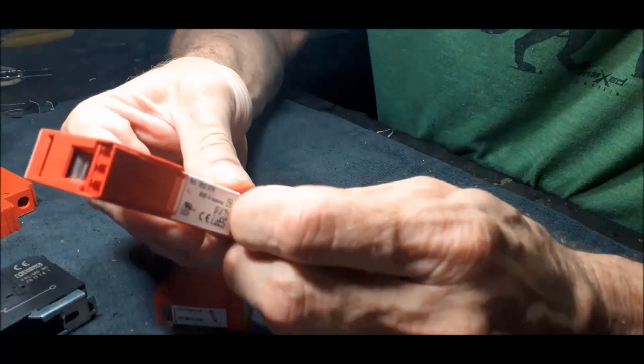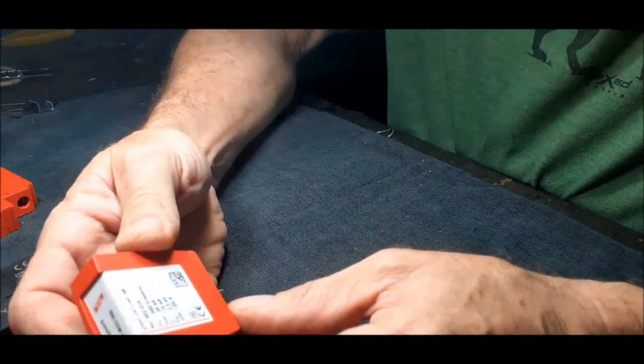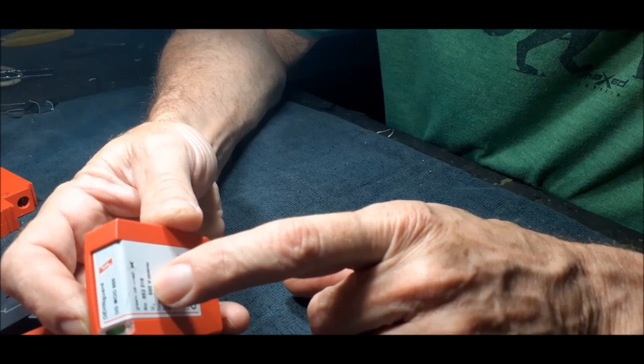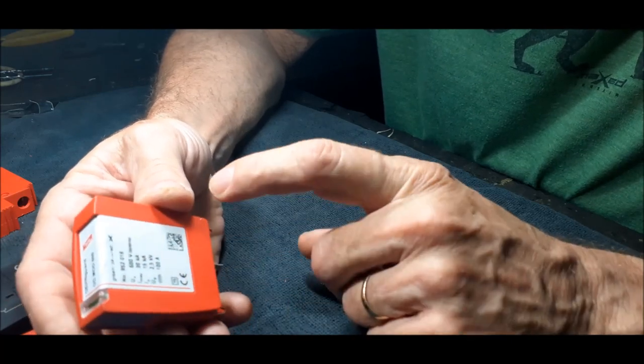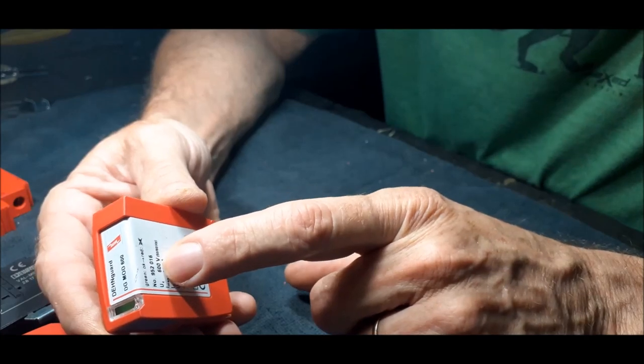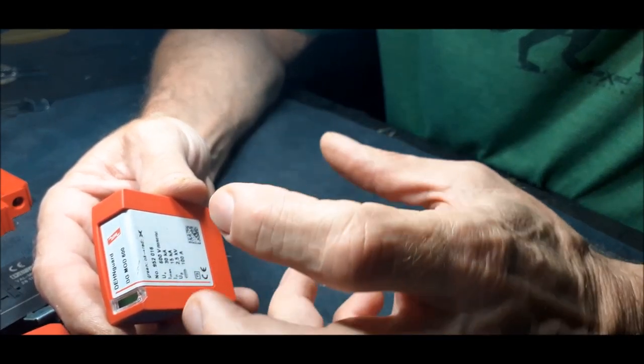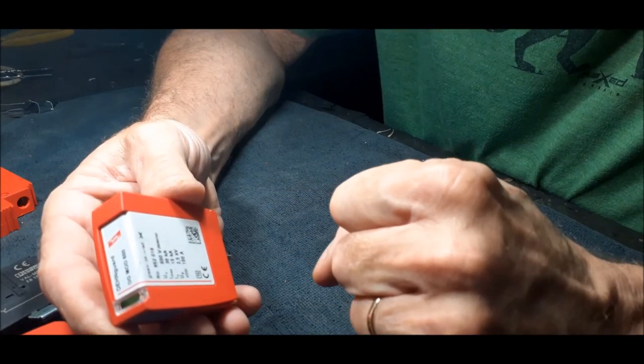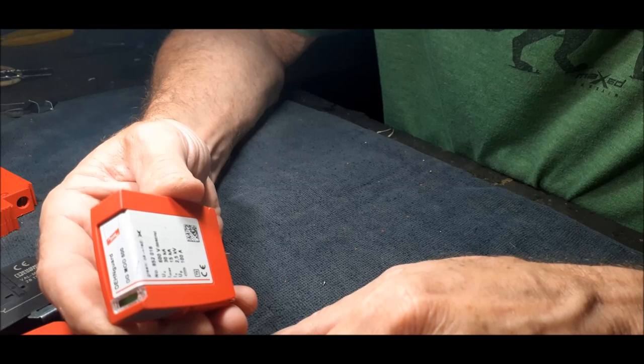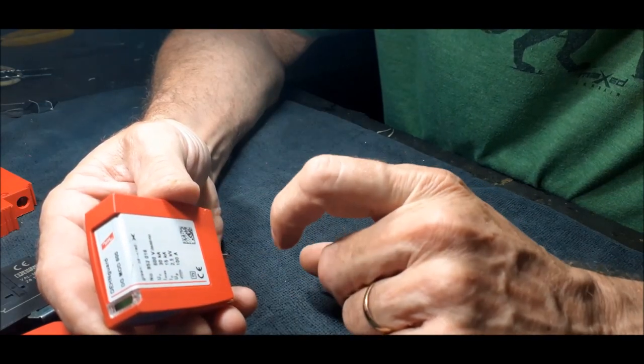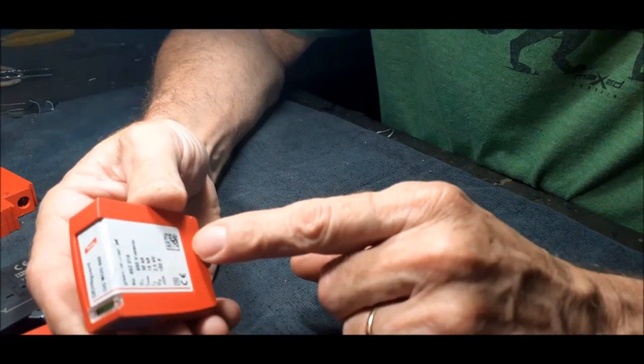Now what you see here, there's obviously clips on a DIN rail inside your DB box. You get different voltage types. You'll see in front here is a 600 volt. So it means when there's a potential of 600 volts over the points, then it will clamp. It is for spikes coming down the power line. It will absorb it and then divert the spike down to ground. We will talk about the connection just now. And then it protects your equipment on the other side of it.